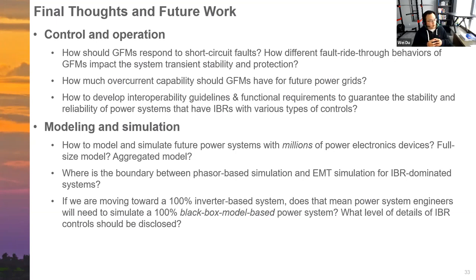And I think we also need to understand how we want them to behave during the fault. It's also a critical thing. A second question is, how much overcurrent capability should grid-forming inverters have for the future power grids? Nowadays, most inverters just have 1.1 or 1.2 overcurrent capability during the fault. But does that really work for the future power grids with 100% inverters, not only grid-forming inverters, but just 100% inverters? Should the inverters still have very low fault current capability? I think we need to rethink this question.